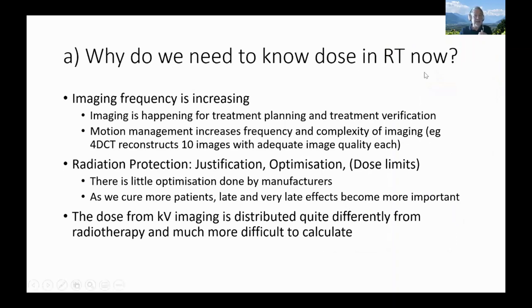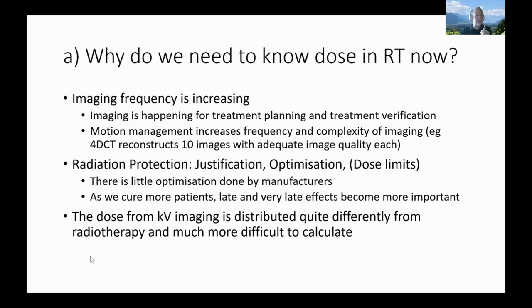Why is this a particular topic now? Imaging frequency is increasing. Virtually every new linear accelerator these days is sold with cone beam CT on board. Radiotherapy also relies much more on certain types of motion management, which increases imaging frequency and complexity. For example, 4D CT reconstructs 10 images — 10 times the dose — hopefully using adequate dose for each phase. Radiation protection is also better understood now, and KV imaging dose is distributed quite differently from radiotherapy dose.